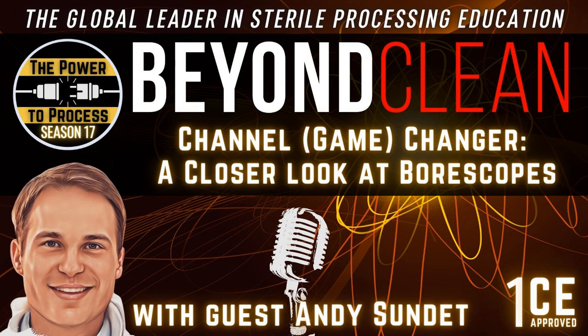And now that borescopes have been out and much more prevalent over the last 10 years, there's been some phenomenal research pointing out, hey, this is a patient-ready scope or device, and this is what it looked like. Are we okay with that? And so I think the findings have led to more industry talk, and things changing on guidelines and IFUs. So I think that's the why to me. Obviously we're a little biased. I think it's a really neat tool to help with this, but there are some really deep whys behind it. The when and where, those are questions that I think we're all working towards.